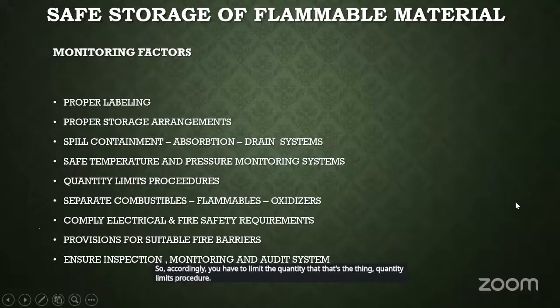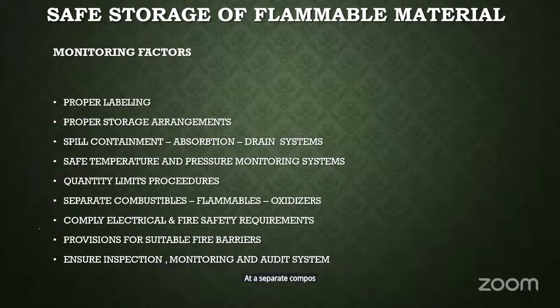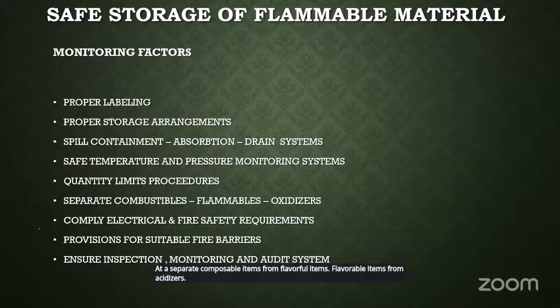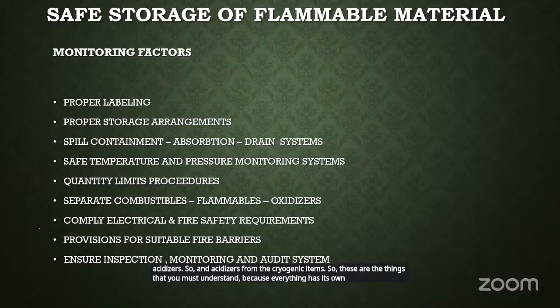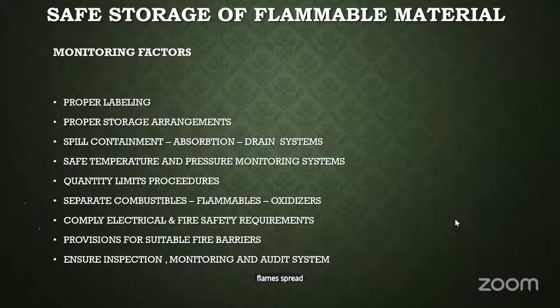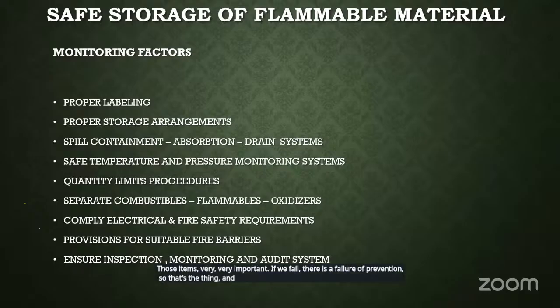Separate combustible items from flammable items, flammable items from oxidizers, and oxidizers from cryogenic items. These are the things you must understand, because everything has its own risk factors, its flame spread varies, and its calorific heat varies. So accordingly, you have to segregate those items. Very, very important. If we fail, there is a failure of prevention. And comply with electrical and fire safety requirements.